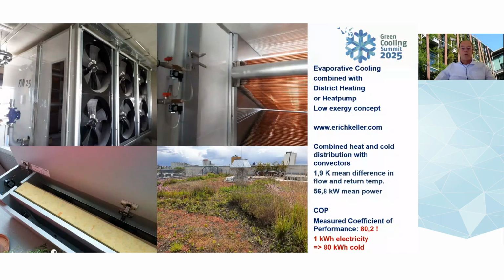In the winter time, the exhaust heat from the servers is used to heat the building, and in the summertime, the cold produced by this system is distributed just by convectors you see on the lower left side. These are convectors which are using just a difference of 2 degrees. So with about 22 degrees, you can cool a building and keep it on 26 degrees. And in winter time, you're using, for example, 25 degrees of heating, and then you can keep the building temperature on 21. So that's all for me.